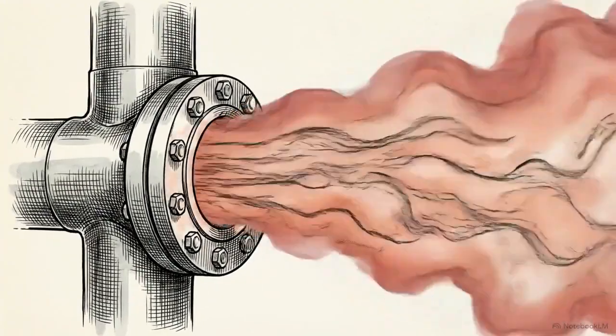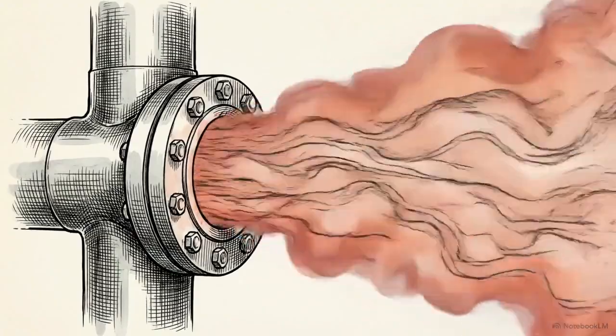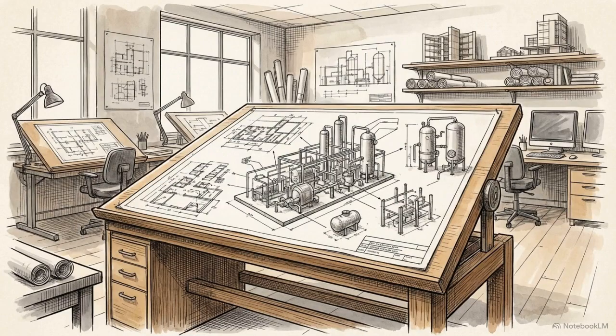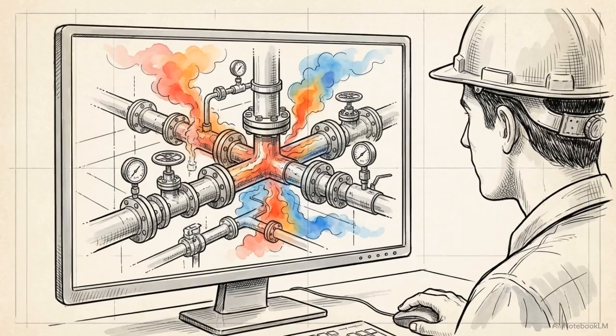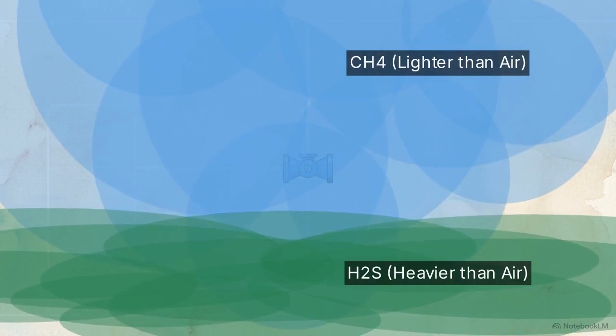A pipe seal ruptures, releasing hazardous gas into a processing unit. Catching this release relies on engineering decisions made years before the plant was even built. System designers must anticipate the specific laws of fluid dynamics for the exact chemical being processed. Gases behave by density. Lighter methane rises rapidly, while toxic hydrogen sulfide sinks to the ground. This dictates hardware placement. High-mounted open-path lasers catch rising flammables, while low-mounted point detectors sense heavy toxics.